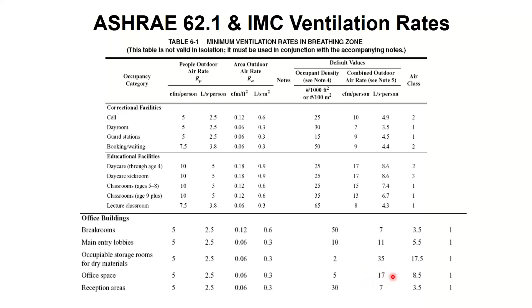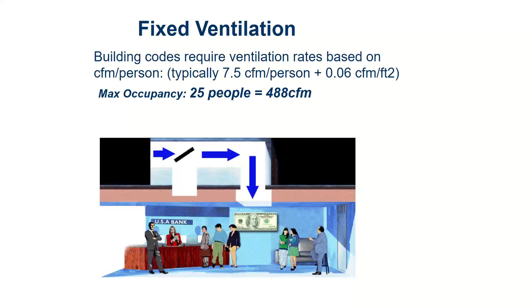So the way demand control ventilation works is you take your space. In this case, it was a retail space, a bank, and that one is 7.5 CFM per person plus 0.06. Whereas if you recall, the office was 5 plus 0.06, the school was 10 plus 0.12. Well, for retail, it's 7.5 plus 0.06. So for this little bank designed for 25 people, with the fire department placard, it would require 488 CFM. But then if 25 people weren't there and there was only 5 people there, which is most of the day, I would have still brought in 488.